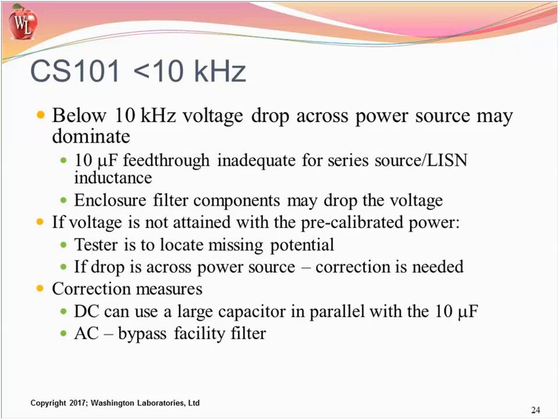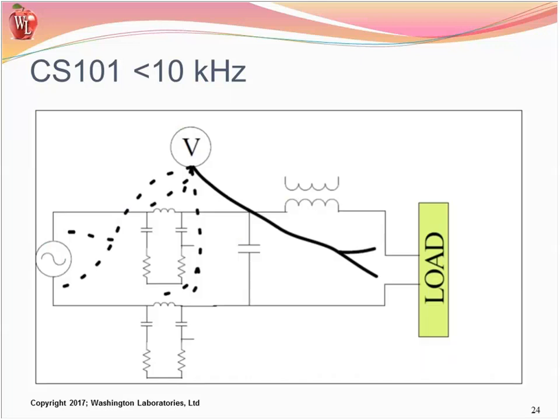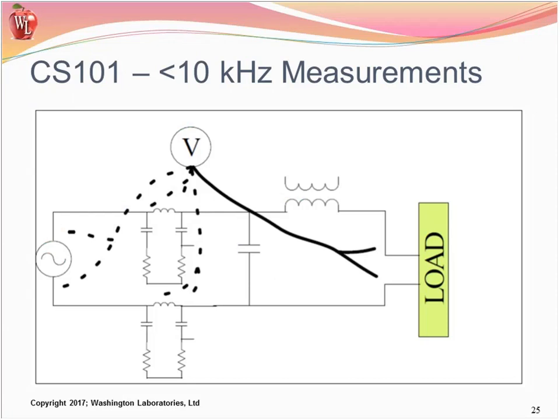So if you don't attain the voltage with the pre-calibrated power level, then you need to locate where the missing voltage is. If the drop is associated with the power source or the feed-through filtering, then you need to do corrective action. Corrective action for DC can use a large capacitor in parallel with the 10 microfarad to lower the frequency of this. For AC, you may need to bypass the facility power filter or go to some other source. So fundamentally, that's what's going on here.